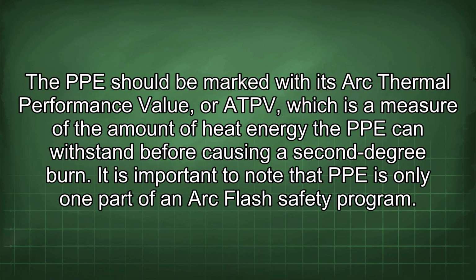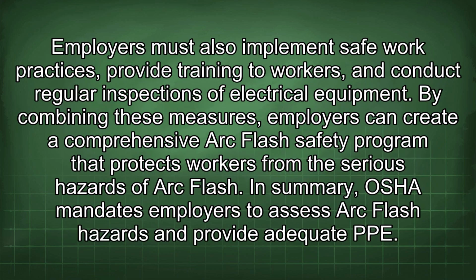The PPE should be marked with its arc thermal performance value, or ATPV, which is a measure of the amount of heat energy the PPE can withstand before causing a second-degree burn. It is important to note that PPE is only one part of an arc flash safety program. Employers must also implement safe work practices, provide training to workers, and conduct regular inspections of electrical equipment. By combining these measures, employers can create a comprehensive arc flash safety program that protects workers from the serious hazards of arc flash.